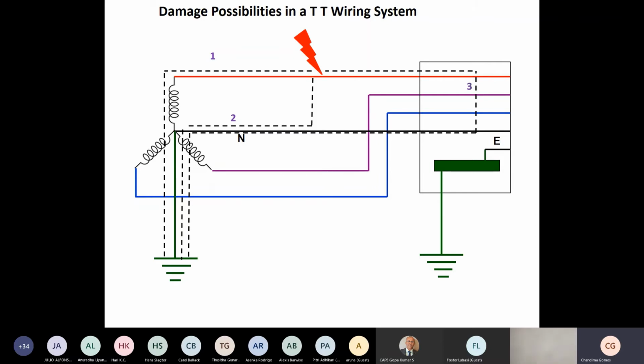Quite a high part of the lightning current may come into your premises, and basically at a distribution board or the main panel, or even inside an equipment, the current may flow from line to neutral and flow into the ground. So this will give rise to a differential mode transient damage. And there is a chance that there may be an arcing inside a power panel, main panel, or distribution board, sub panel, an arc happening from line to neutral. And this is the other way.